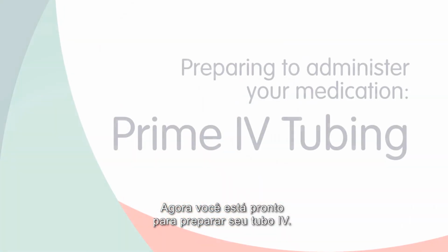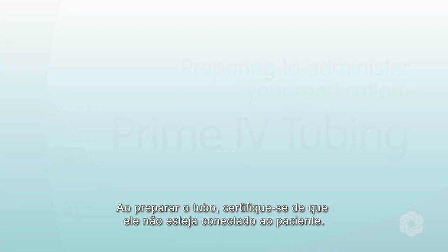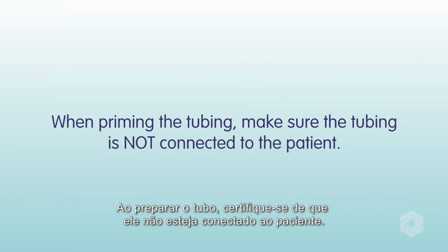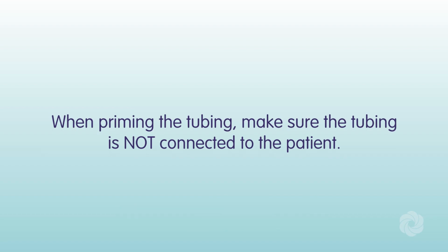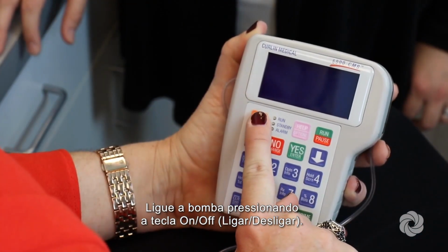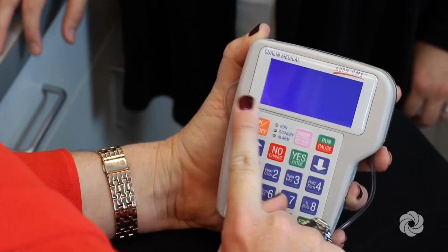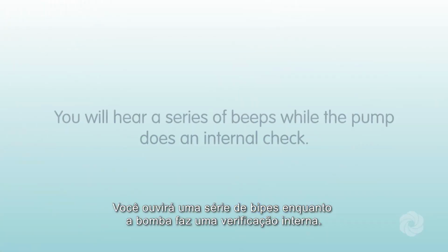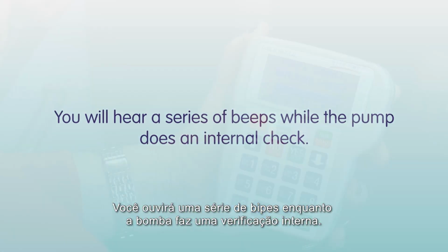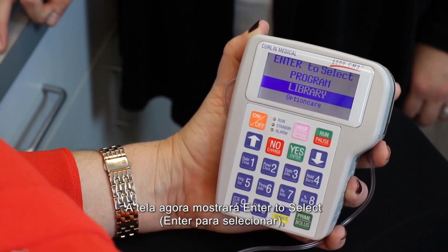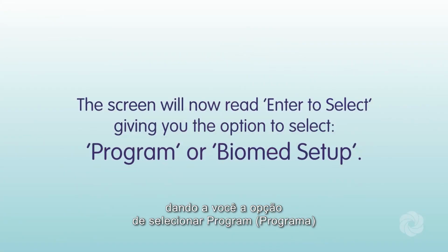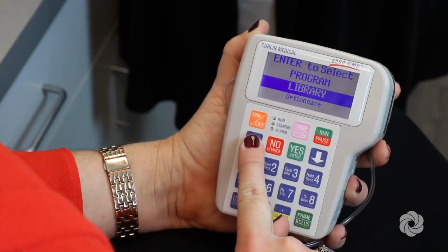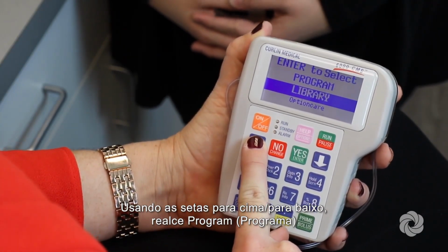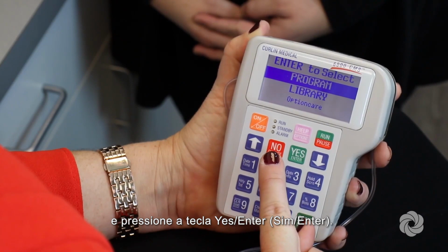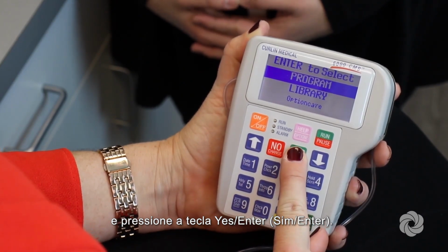You are now ready to prime your IV tubing. When priming the tubing, make sure the tubing is not connected to the patient. Turn the pump on by pressing the on-off key. You will hear a series of beeps while the pump does an internal check. The screen will now read Enter to Select, giving you the option to select Program or Biomed Setup. Using the up-down arrows, highlight Program, followed by pressing the Yes Enter key.